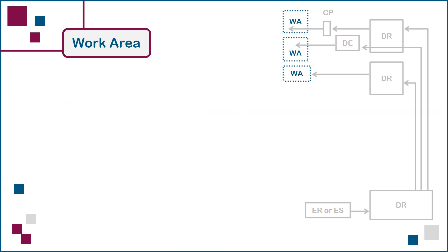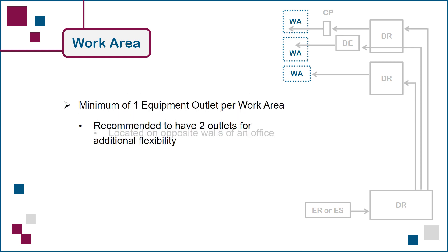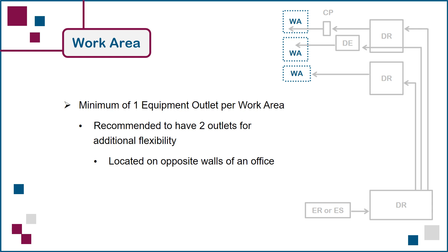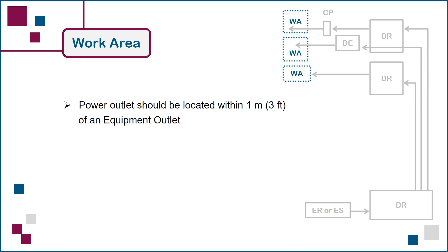The design for each work area should have at least one equipment outlet, with two outlets recommended for enclosed offices to facilitate the arrangement of desks, workstations, and devices such as desktop computers and phones. And there should be coordinated placement of equipment outlets and electrical power outlets to make both equally accessible to nearby devices.